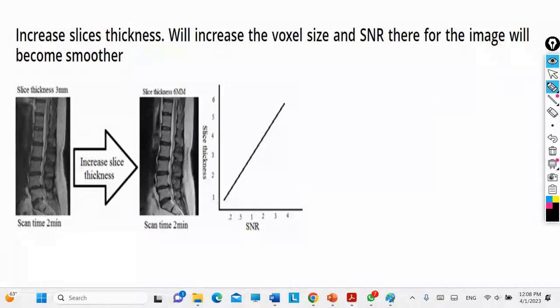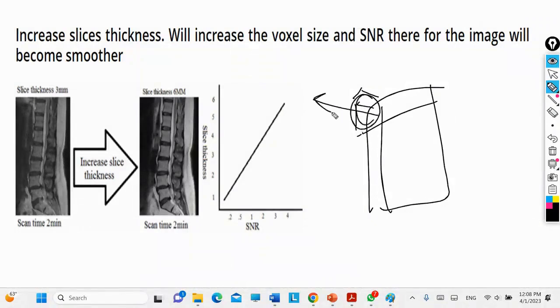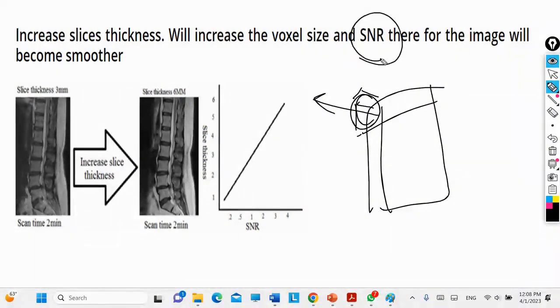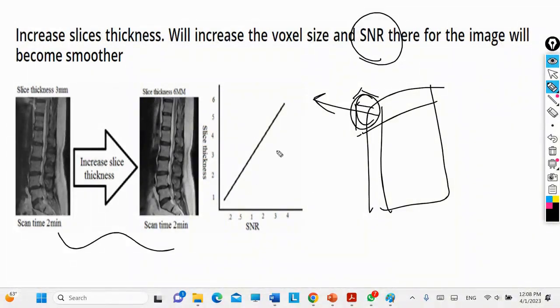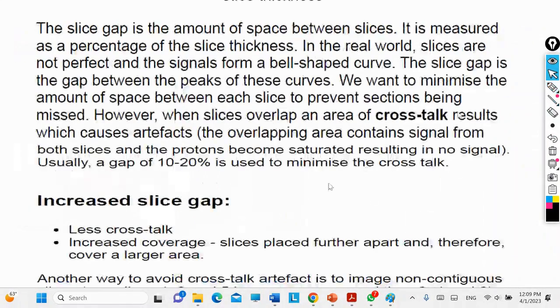Increasing the slice thickness also affects the voxel — the three-dimensional volume element. When you enlarge the slice you are taking, the voxel size increases. As a result, the signal-to-noise ratio (SNR) becomes higher, meaning an increase in slice thickness leads to an increase in SNR.